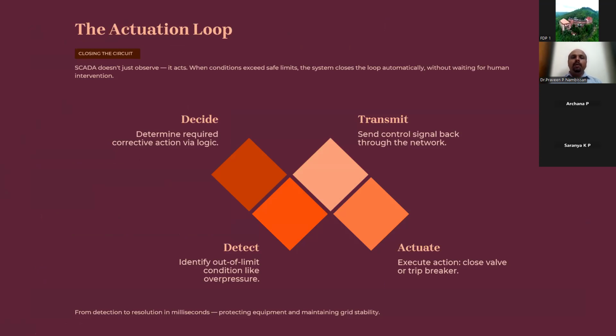Then the actuation loop. When a SCADA system works, it is not just observing, it acts. When conditions exceed the safe limit, the system closes the loop automatically without waiting for human intervention. That means detect, then decision, then transmission, then actuation, without any human intervention. If there is an error, it will detect, decide what to do, then transmit the signal to the actuator, then the actuator will actuate and the process will shut down if required. So necessary action will take place.